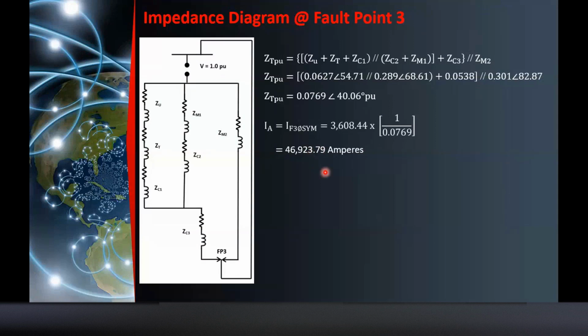Okay? For impedance diagram at fault point 3, so kanina yung nauna natin, ito yung main bus. Kanina ito yung kinumpute natin na faulted point. Ngayon naman doon sa pangalawang feeder. So ZU, ZT, Z cable 1 in series. ZM1, ZC2 in series. Parallel in series with your Z cable 3 kasi nandun yung faulted point. Parallel naman siya sa Z motor 2. So pag ginawa mo yan, series parallel, reduction, you will get 0.0769 angle 40.6. And the fault current is 46,923.